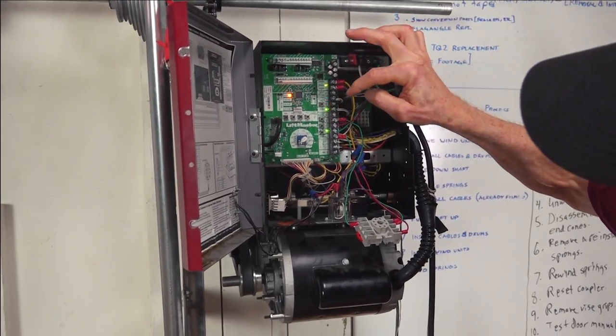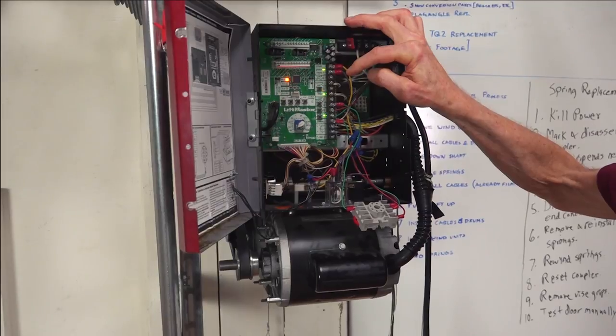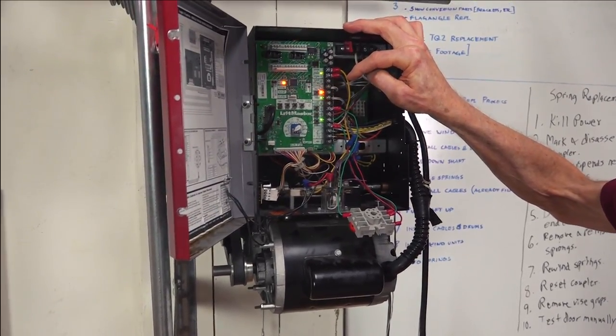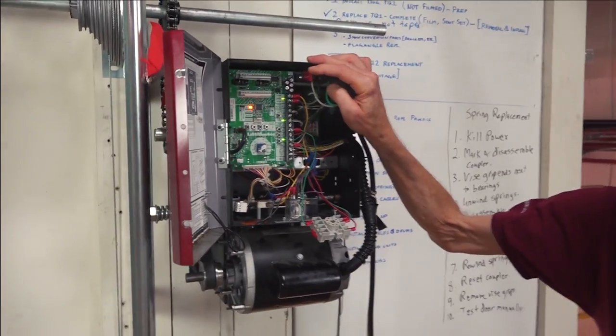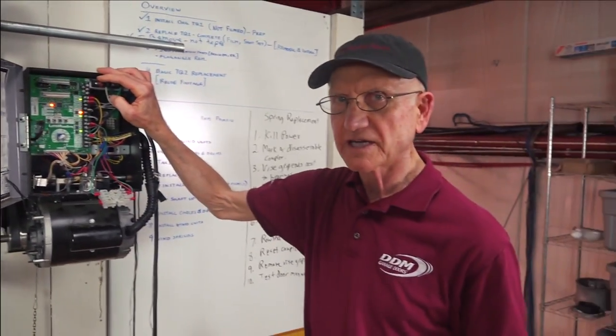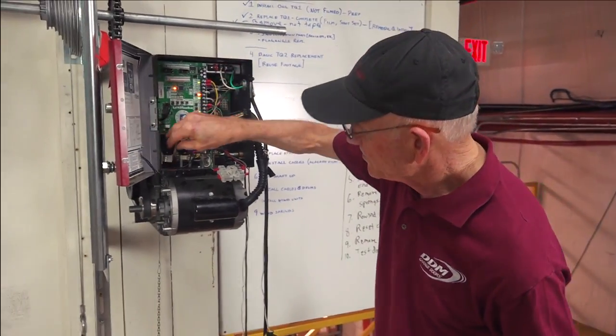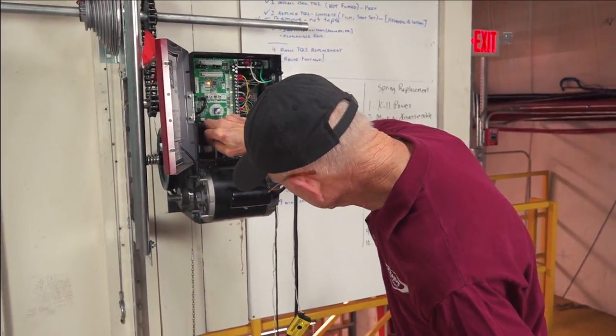Notice four flashes, four blinks. The four blinks tell you that the RPM sensor has been activated. And our demonstration will reconnect the RPM sensor.